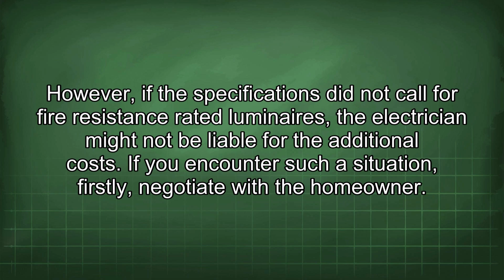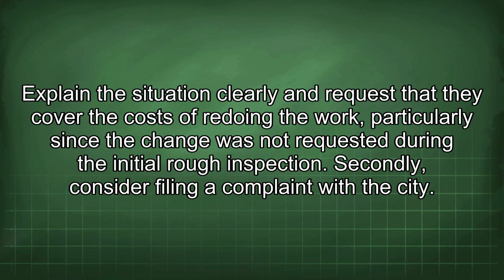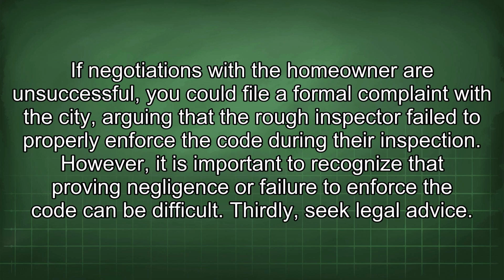However, if the specifications did not call for fire resistance rated luminaires, the electrician might not be liable for the additional costs. If you encounter such a situation, firstly negotiate with the homeowner. Explain the situation clearly and request that they cover the costs of redoing the work, particularly since the change was not requested during the initial rough inspection. Secondly, consider filing a complaint with the city. If negotiations with the homeowner are unsuccessful, you could file a formal complaint with the city arguing that the rough inspector failed to properly enforce the code during their inspection.